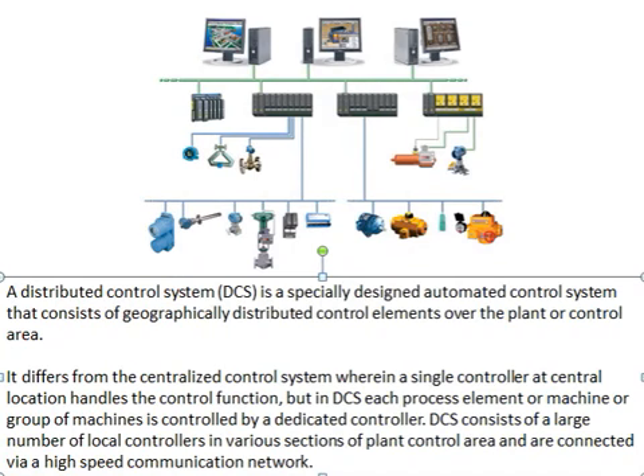A distributed control system, DCS, is a specially designed automated control system that consists of geographically distributed control elements over the plant or control area. It differs from the centralized control system, wherein a single controller at a central location handles the control function. In DCS, each process element or machine or group of machines is controlled by a dedicated controller. DCS consists of a large number of local controllers in various sections of the plant control area, connected via a high-speed communication network.